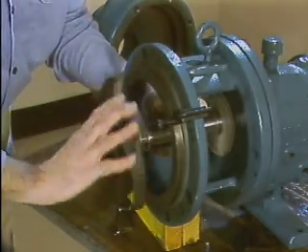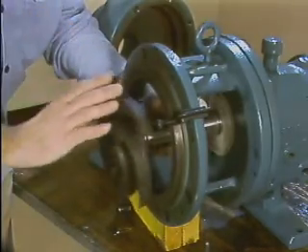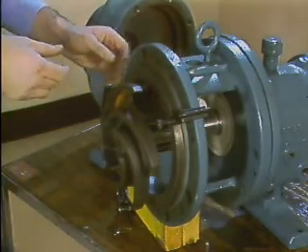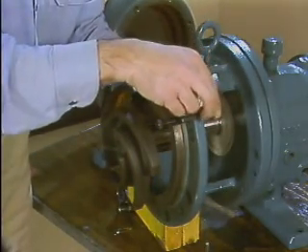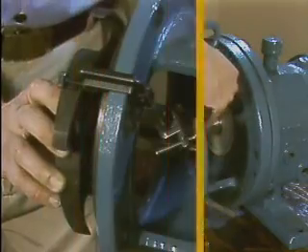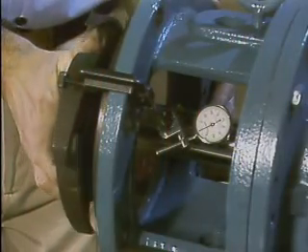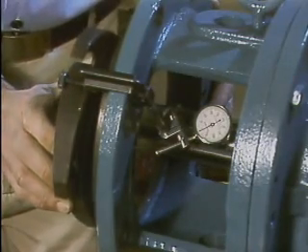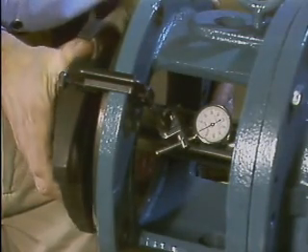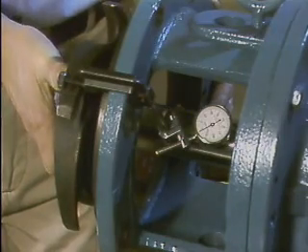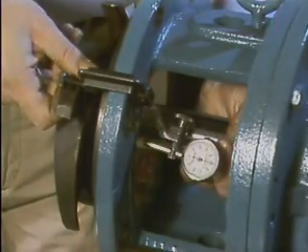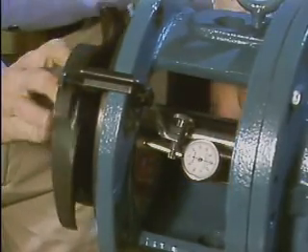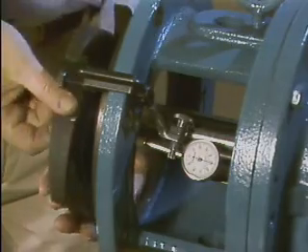Next, sleeve runout is checked. Basically, this is done by installing the shaft sleeve in the impeller, which holds the sleeve in place, then repeating the process that's used for measuring shaft runout with a dial indicator. Checking sleeve runout is important because the seal's rotating element is mounted on the sleeve. Excessive sleeve runout could prevent the rotating element from being properly positioned next to the mating ring. Once the sleeve runout check is complete, the impeller and the sleeve are removed from the shaft again so that other checks can be made.